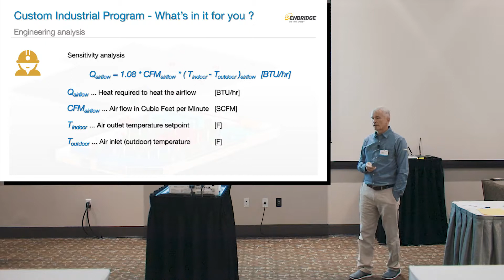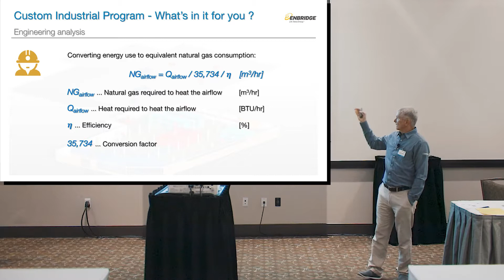So if we put in 20,000 CFM, and say that we want to heat it to 72 degrees F, and that the average outdoor temperature is 38.4 degrees, which it is in the GTA for the typical year, then I can tell you for a fact that you're going to use 725,760 BTUs per hour to heat that, as long as we know that those are correct inputs. So if we convert that to natural gas and use some efficiency, the natural gas required to heat the airflow is NG airflow. Heat required comes in. Efficiency of the unit is eta, and the conversion factor is just to get from BTUs to cubic meters per hour. That's how much natural gas we'll use. So again, we put in all those inputs: 22 cubic meters per hour. This particular unit, 20,000 CFM, gets you 22 cubic meters per hour. That's a given.